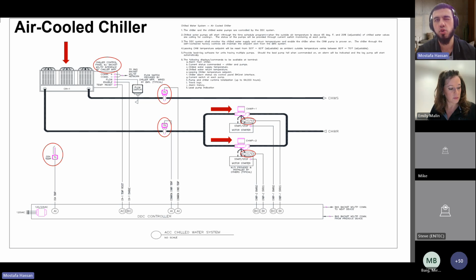So you're saying wiring directly to the DDC system. In both scenarios, you're hardwiring to the controller, whether coming from the VFD or, if there is no VFD, just wiring to the current switch and relay, making sure that the pump is on and that it's actually working. Like Emily said, there isn't really much disadvantage, besides the fact that it's much easier to do it through the VFD because you're also collecting more points, and you're able to calculate virtual points like runtime by monitoring the VFD. So the disadvantage is not using the available VFD backend interface, if there is one. It comes down to that.